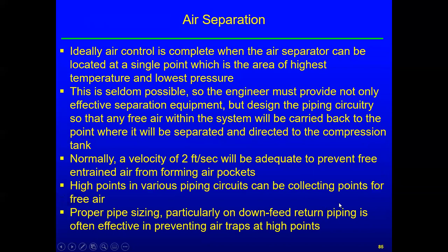Ideally, air control is complete and the air separation point is the area of highest temperature and lowest pressure. Well, wouldn't that be nice? I'm not sure how often that's possible. And so we're going to have to make some judgments here. This is seldom possible. So the engineer must provide not only effective separation equipment, but design the piping circuitry so that any free air within the system will be carried back to the point where it will be separated and directed to the compression tank.